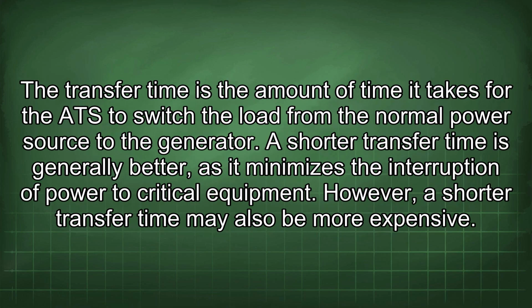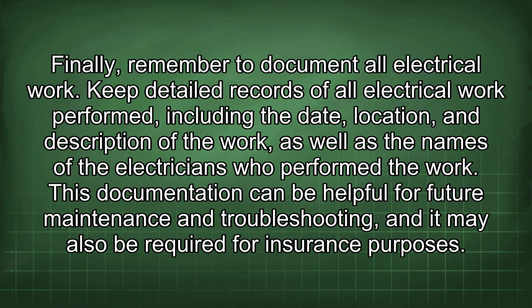The transfer time is the amount of time it takes for the ATS to switch the load from the normal power source to the generator. A shorter transfer time is generally better, as it minimizes the interruption of power to critical equipment. However, a shorter transfer time may also be more expensive. Finally, remember to document all electrical work.